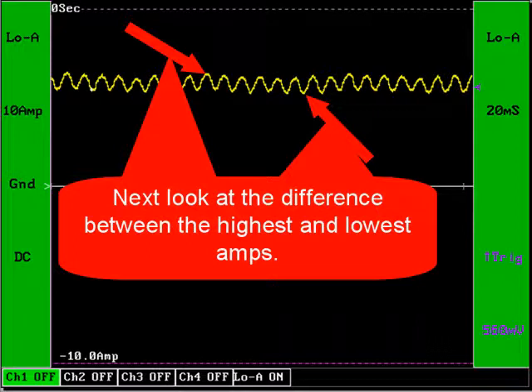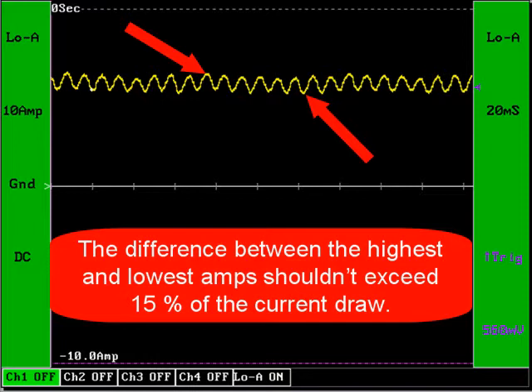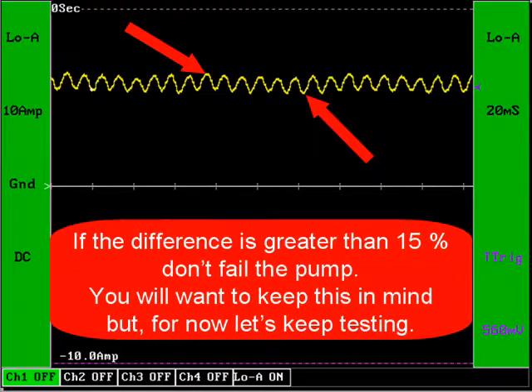Next, you want to look at the difference between the highest and the lowest amps. And you can see here that the difference between our highest and lowest amps in our example does not exceed the maximum. And the maximum is 15% of the average current draw. In fact, we have a very good looking waveform here. If the difference is greater than 15%, don't fail the pump just yet. Once again, keep it in mind and continue testing.